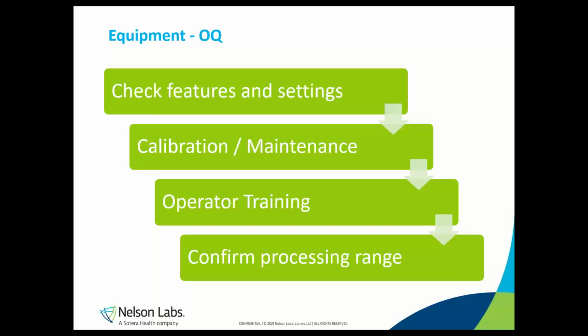Once you have the processing window selected, then you verify the quality of the seals using the seal integrity and seal strength tests at the high, the nominal, and the low settings. If you can show that you have acceptable data through the processing window, meaning we make good seals at the low and the high ends, then we can move to the PQ. If there are failures, then we need to investigate to determine what happened and why. If the high or the low end fails, then we can adjust the processing window and start over.